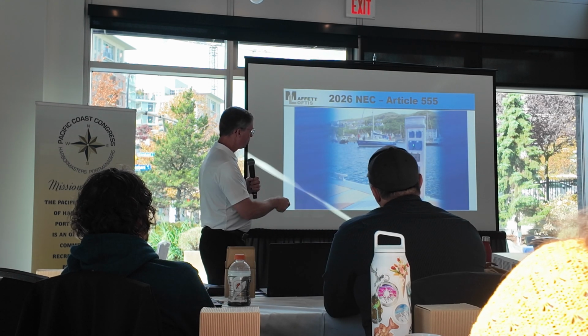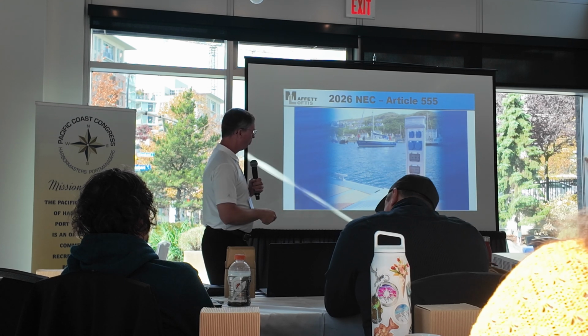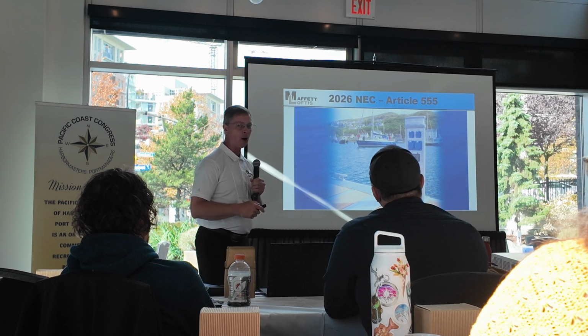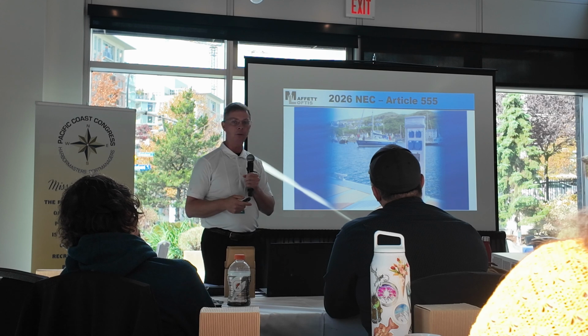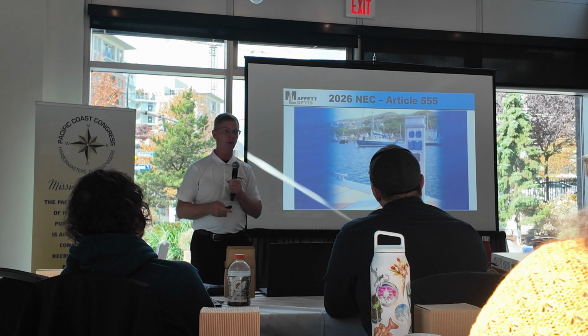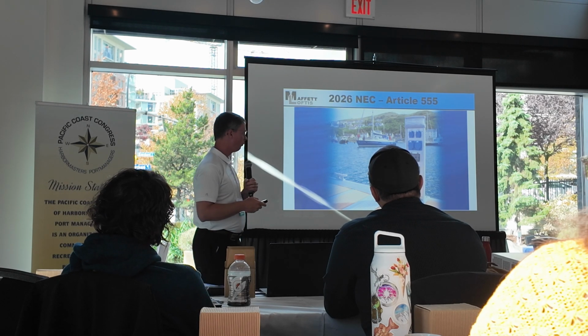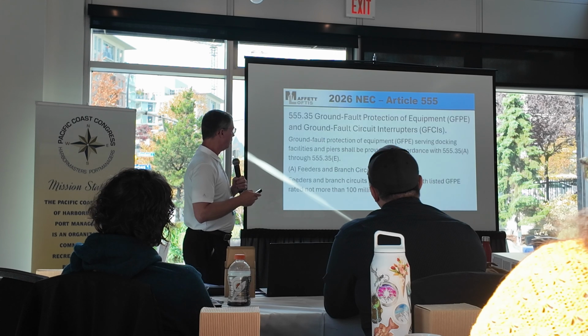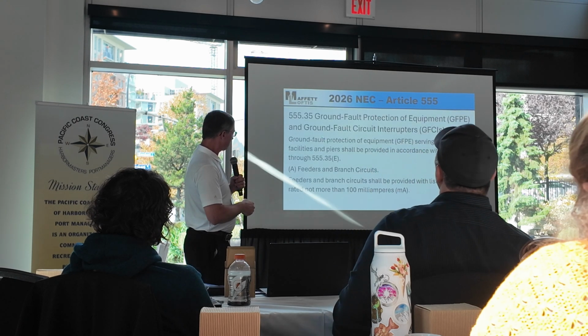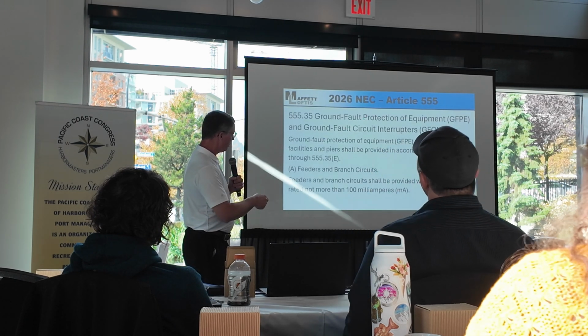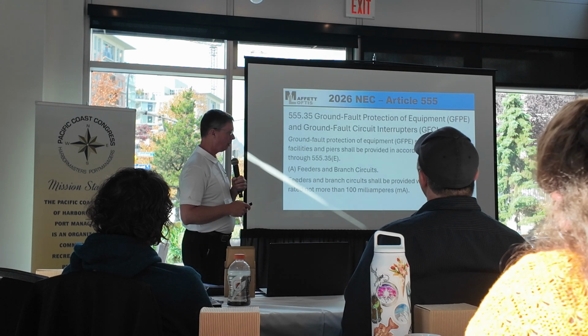And here, the pedestal does not have any 20 amp on it, so that pedestal manufacturer would have to now, because of this code, put a 20 amp, 15 to 20 amp maintenance GFCI receptacle on it. Force them to do that. Okay, this is, nothing changed in this, but I'm displaying this for a reason.